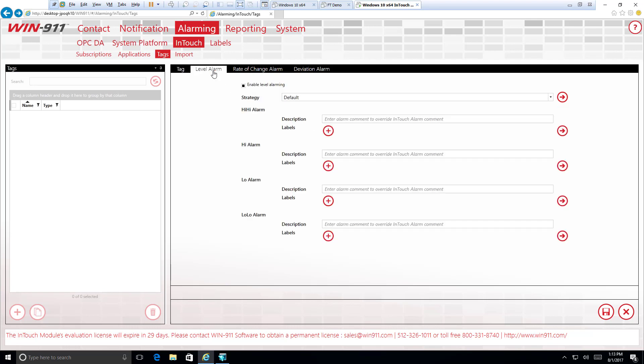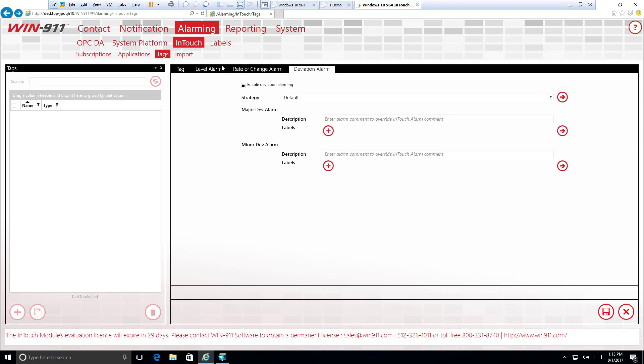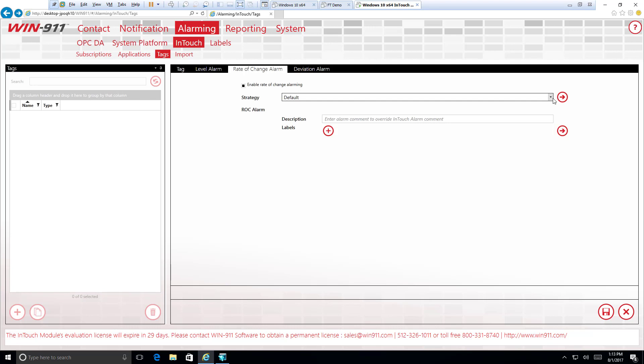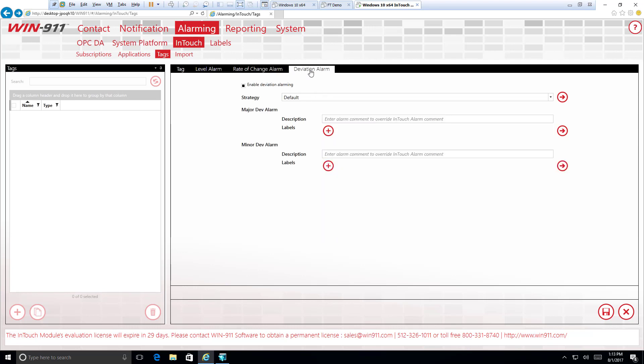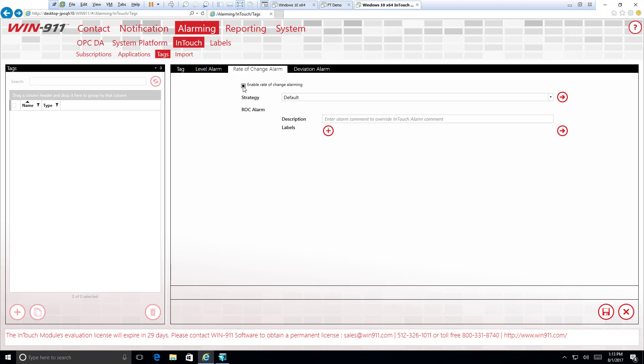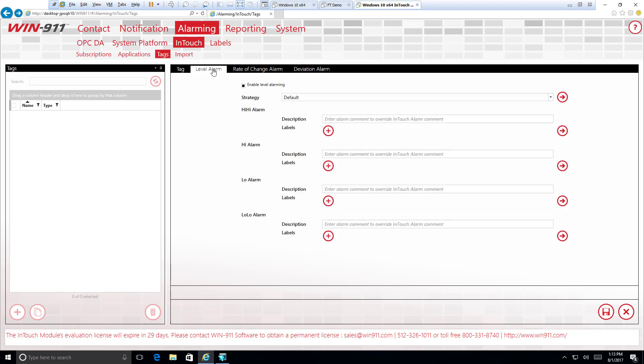You'll see here we have three different tabs for our level alarm, rate of change, and deviation. We know that the rate of change and deviation alarms don't exist within this reactor temp tag. But we can take a look at them anyway to just see what exactly we would need. Really, all we're going to need here for the rate of change is a strategy to accomplish whenever we see that alarm go off. And once again, a description that we can override the default description with. And some labels once again. Very similar for our deviation, except now we have a major deviation alarm to describe using a description and labels, as well as a minor deviation alarm to describe using description and labels. But for now, since those do not exist for this tag, we will go here and disable each one of these and head over to our level alarm.